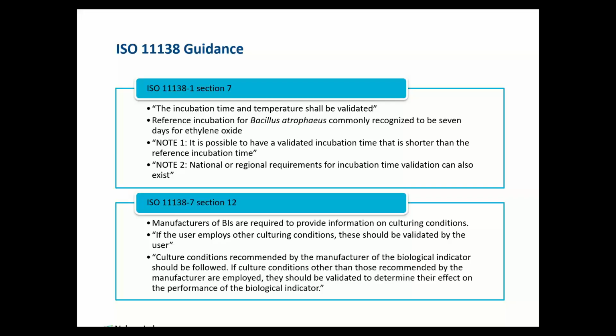This section also states that culture conditions recommended by the manufacturer of the biological indicator should be followed. So again, use of the word should. If culture conditions other than those recommended by the manufacturer are employed, they should be validated to determine their effect on the performance of the biological indicator. So again, with the validation that Nelson Labs performed, this is exactly what we were addressing, the performance of the BI in relation to each of those parameters that were outlined.